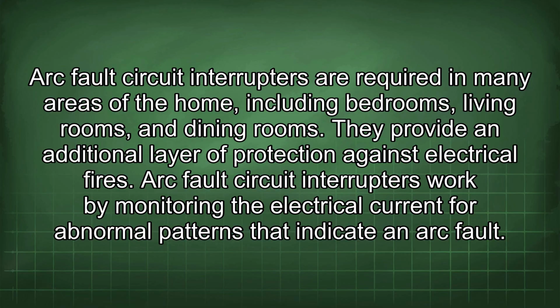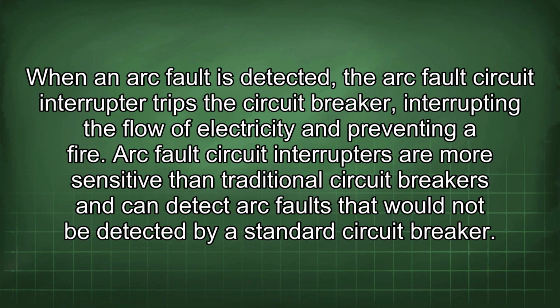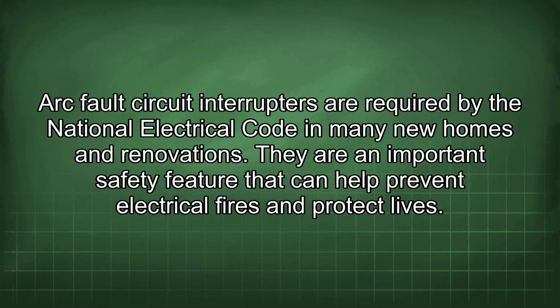Arc fault circuit interrupters work by monitoring the electrical current for abnormal patterns that indicate an arc fault. When an arc fault is detected, the arc fault circuit interrupter trips the circuit breaker, interrupting the flow of electricity and preventing a fire. Arc fault circuit interrupters are more sensitive than traditional circuit breakers and can detect arc faults that would not be detected by a standard circuit breaker. They are required by the National Electrical Code in many new homes and renovations. They are an important safety feature that can help prevent electrical fires and protect lives.